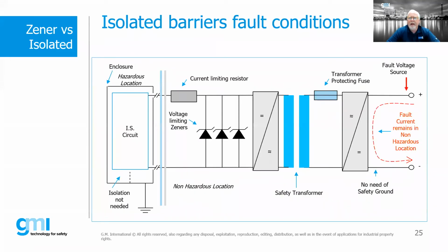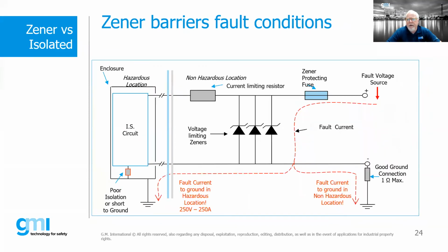So when we look at an isolated barrier under a fault condition, what happens? It hits the transformer, it stays in the safe area. We never have a point where, say, if the cable was cut or something like that, we had a fault condition within the hazardous location, because our safety transformer, in effect, has limited the current going into the hazardous area.